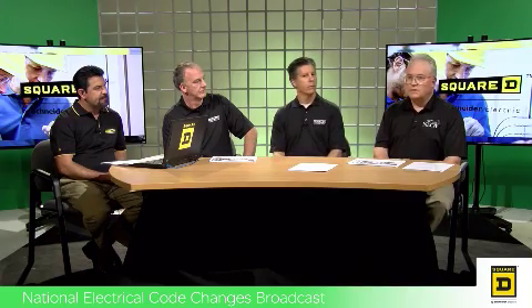As far as the floor receptacles, the requirement applies where you have a meeting room that's over 12 feet in width, and you end up with a square footage of somewhere around 215 square feet. When you have that amount of area, you have to add an additional floor receptacle. It's also anticipated that you may deal with portable or movable partitions that may divide the space, so the floor receptacles come in handy to not leave a space without a receptacle if the partitions are in place.